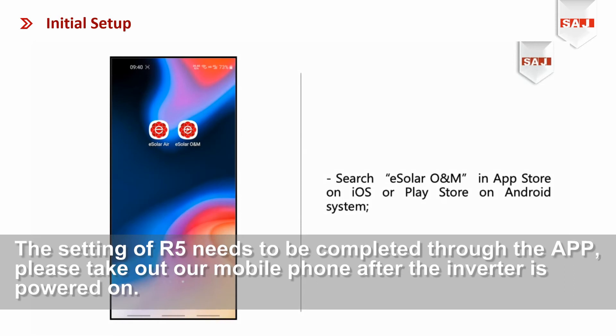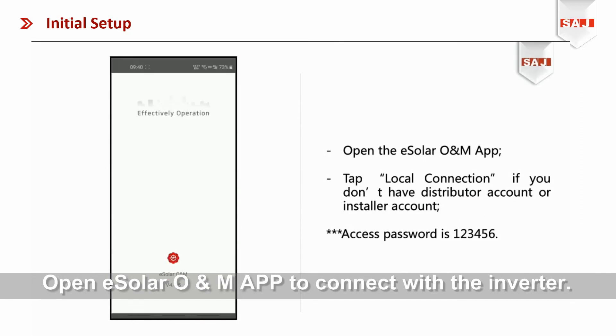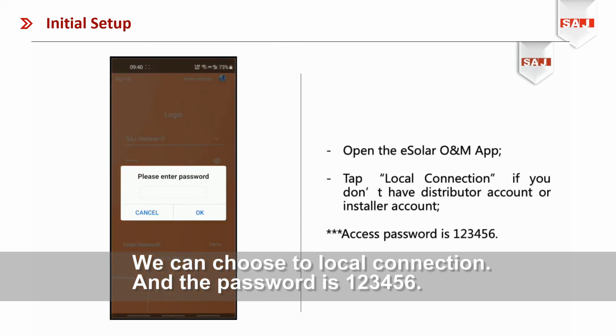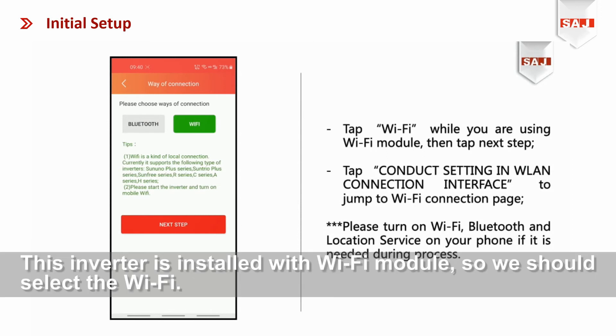The commissioning of R5 needs to be completed through the app. Please take out your mobile phone after the inverter is powered on. Open the eSolar O&M app to connect with the inverter. You can choose a local connection and the password is 123456. This inverter is installed with a Wi-Fi module, so we should select Wi-Fi.